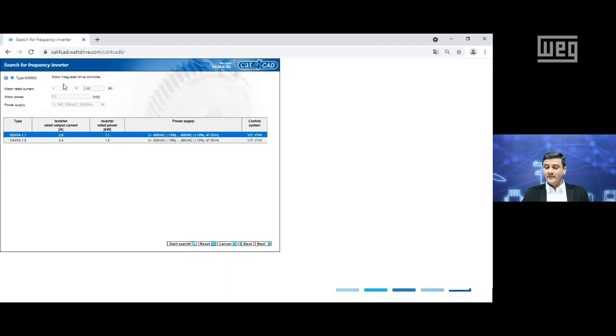Next. And from this screen, you start seeing the motor data. As you can see, for the selected motor here, the motor rated current is 2.4 amps, the motor power 1.1, the power supply three-phase as we chose. And for the inverter data, you can see the inverter rated output current. So the software gives me here two options. One, which is output current 2.6, and the second, which is 3.4. In this case, the motor rated current is 2.4. So we're going to consider 2.6.